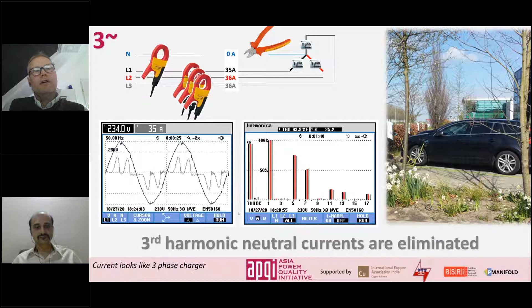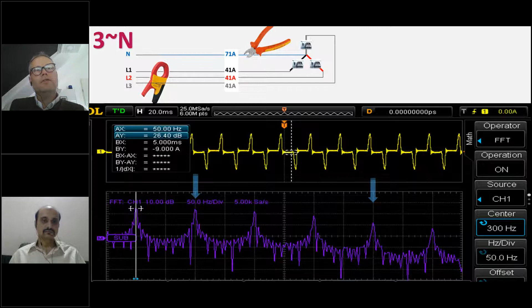So, one slide back, here we have the 3rd harmonic, the 9th harmonic and the 15th harmonic gone because our neutral wire was cut or melted down. And here are our original marks. This is the 3rd harmonic, and this is the 9th harmonic. Now when we cut the neutral, this will happen. Here you will see the 9th and the 3rd harmonic have vanished. The 5th and the 7th harmonic are still there.